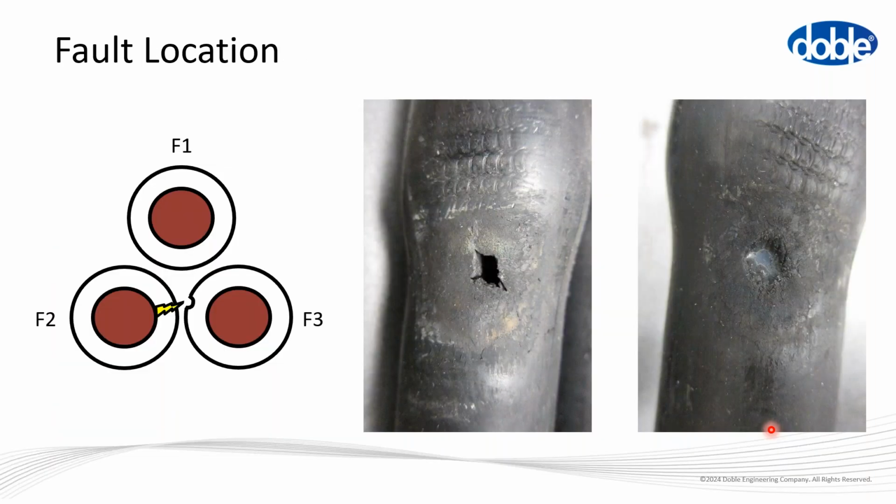Now, interestingly, I said we started with the healthy cable. When we took the 3 joints out of the healthy cable, this is what we found. We found the fault path. This is the importance of labeling things carefully. The client who shipped the samples to me mislabeled the cables. They had a 50-50 chance of getting the label on the right cable, but they failed that. So we were very lucky.